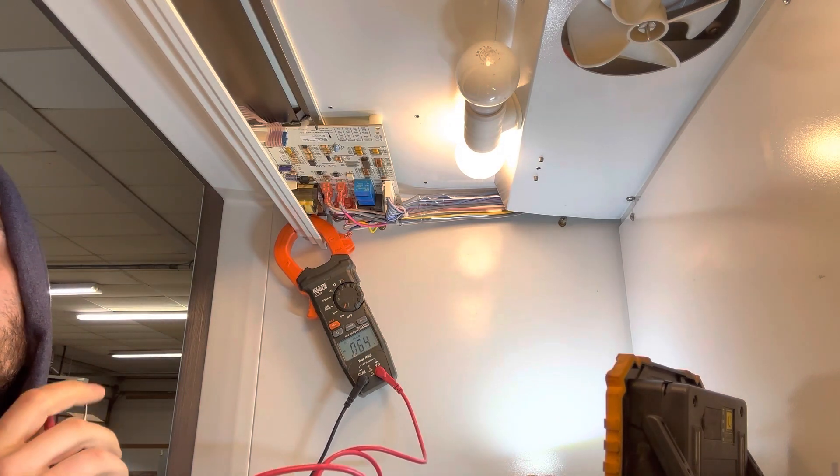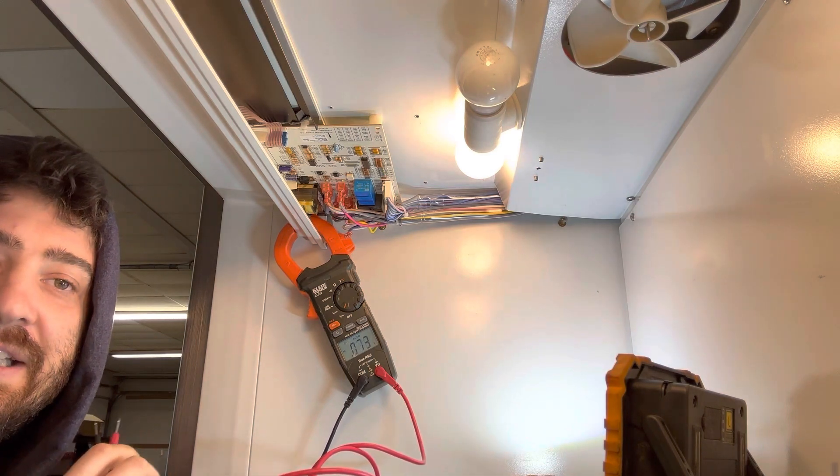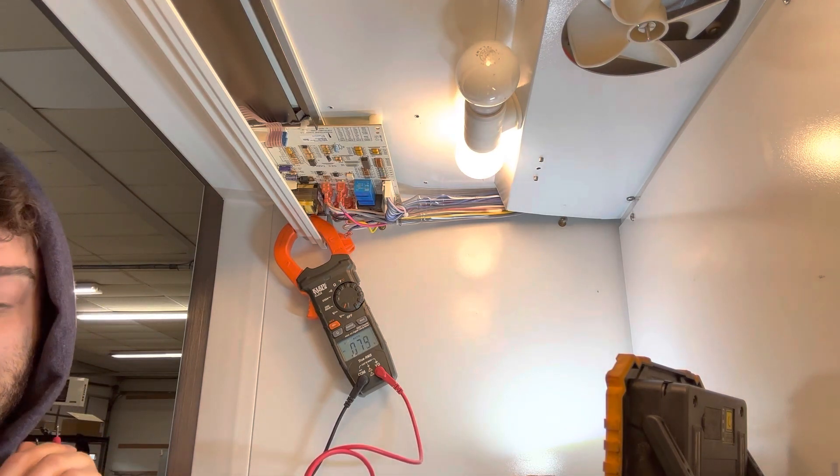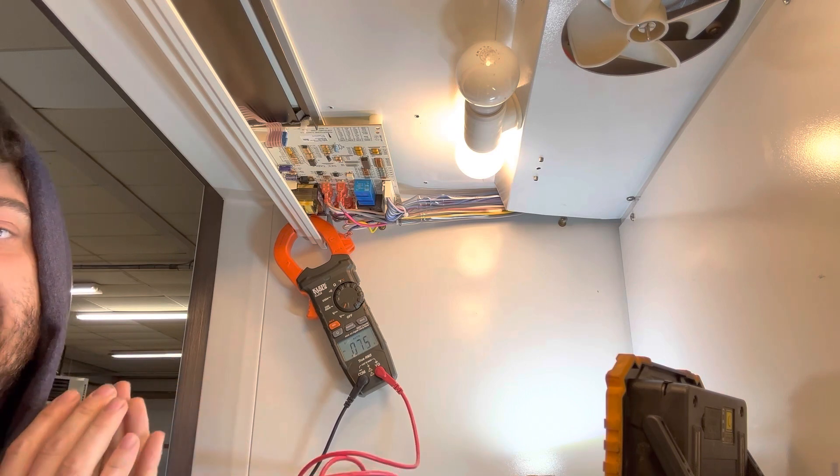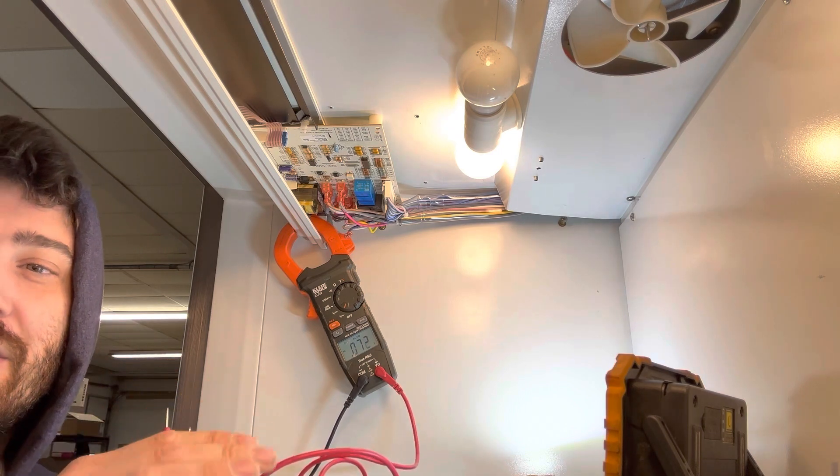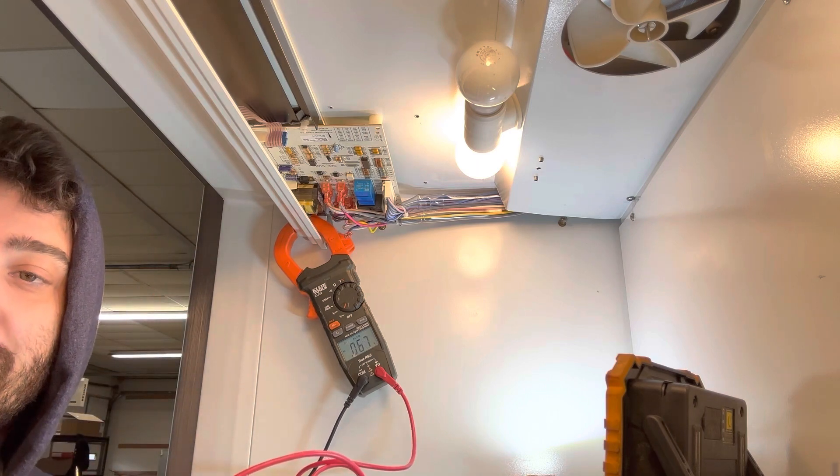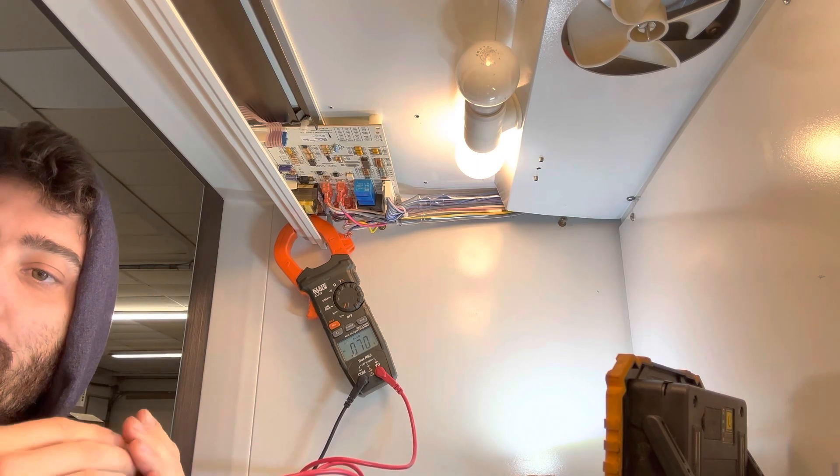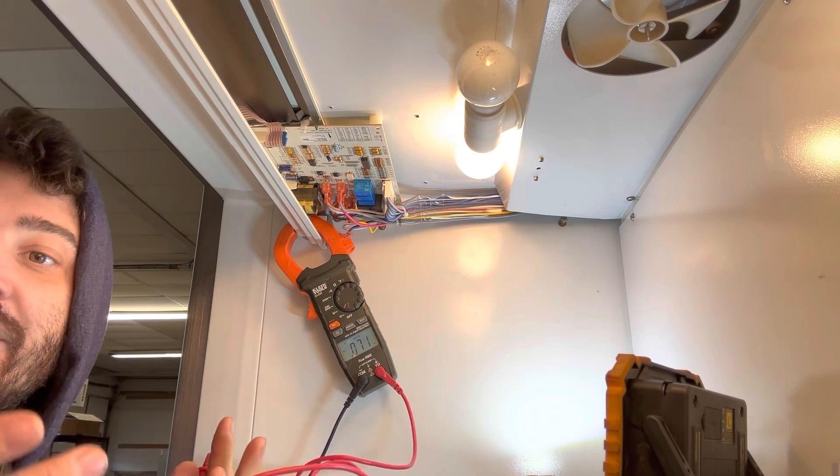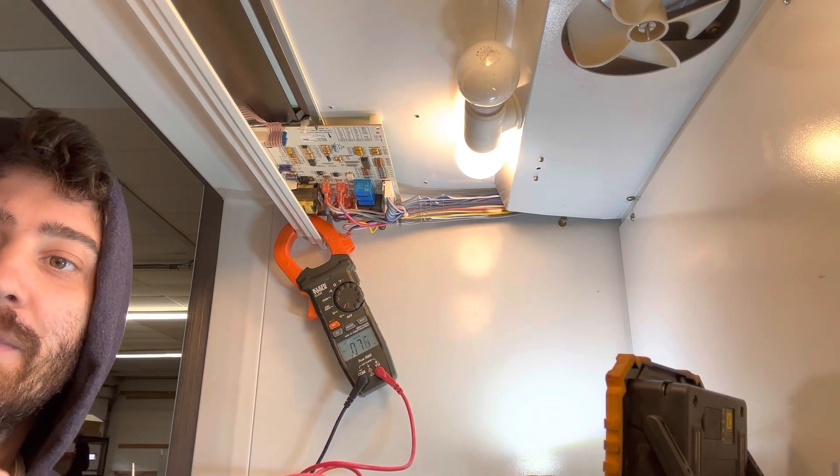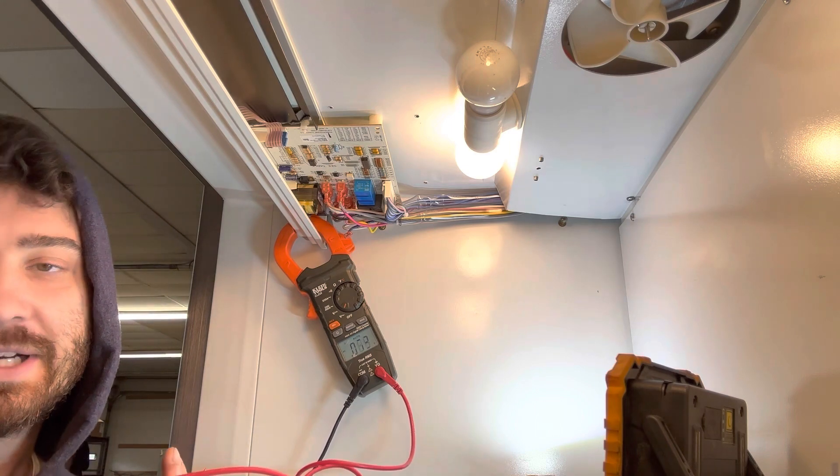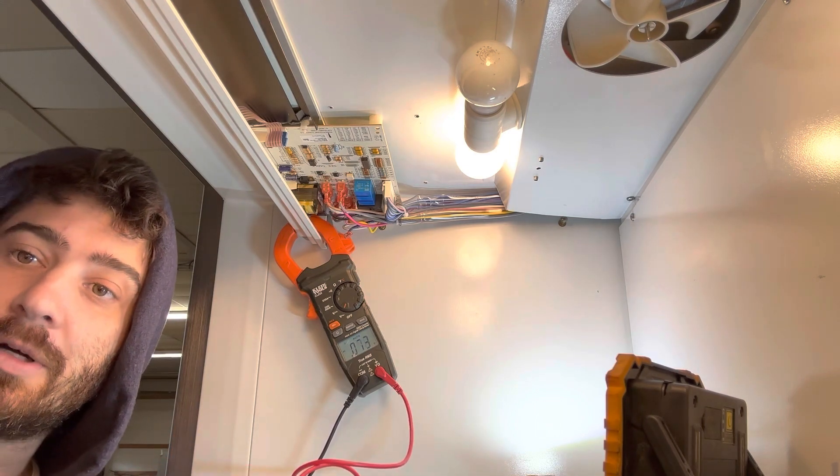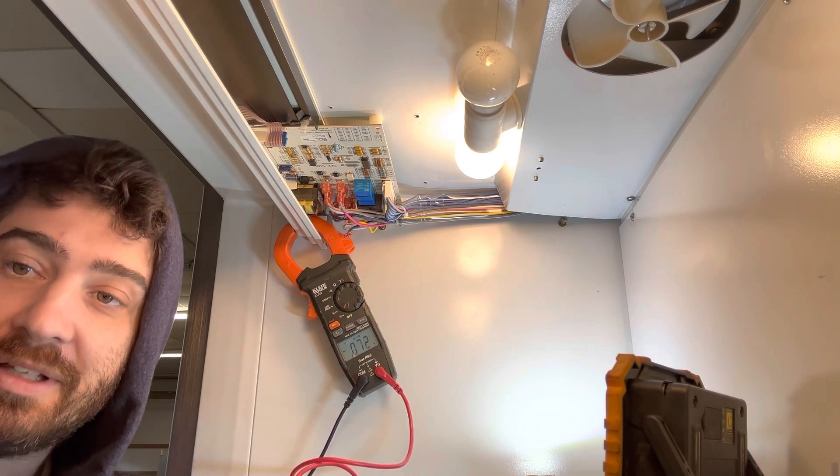Does that mean the control board's good? More than likely, yes. Could the control board not be going into defrost on its own only when I do it manually? Yes, but more times than not, no. We've passed the test. The control board is sending 120 volts when I tell it to. Let's make our way down the schematic to our next spot, the defrost terminator, and determine whether we're getting the voltage from the board all the way to the terminator. Could there be a break in the line before the terminator? Could the terminator be getting power and not just be doing its job? Yes, so let's go look.